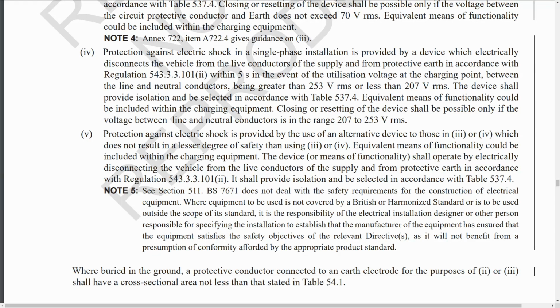Now we move on to the two here at the end, number 4 and 5. These are entirely new and did not exist previously, so we've got a couple of extra options here. That's pretty good because the previous options are so unlikely and implausible that really nobody was going to use them anyway. Now, number 4, protection against electric shock in a single-phase installation is provided by a device which electrically disconnects the vehicle from the live conductors of supply and from protective earth, in accordance with the regulation in 5 seconds.